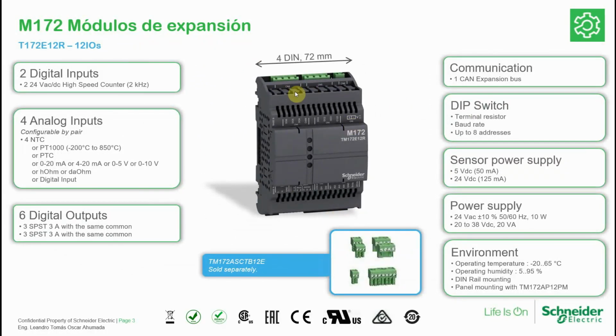Here you can see that the PLC doesn't come with any block. We need to buy it separately. This is the reference for this model. The communication between the module and the PLC is over CAN, so we need to communicate using CAN. And we have some dip switches to select the address in the communication and the parameters of the communication. These are details for the analog inputs and digital IOs.